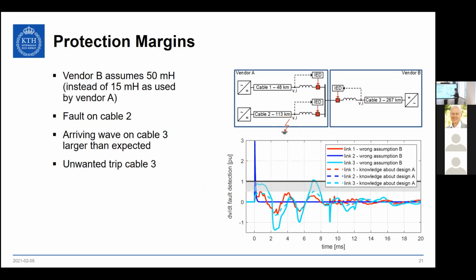There you can also see the red signal. That's the fault detection on the neighboring cable of the same vendor A, and you see a disturbance from the fault, but it doesn't go near the threshold. You can also see how it still has a certain margin to the threshold as required by design. But on the new link with the new vendor B, who didn't know the line inductor size, that one designed the fault detection as shown in turquoise here.